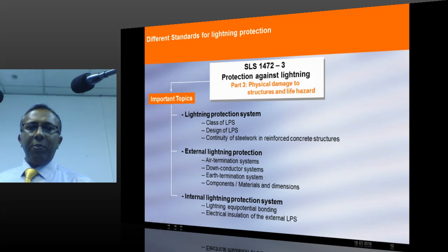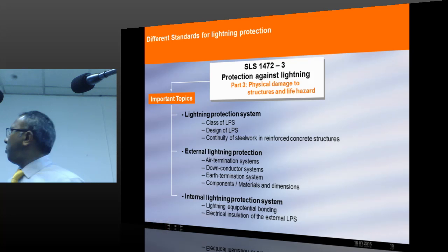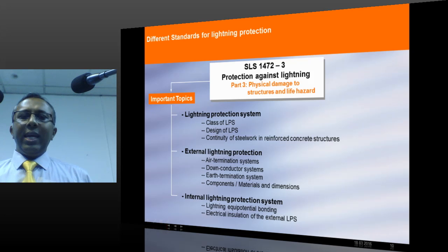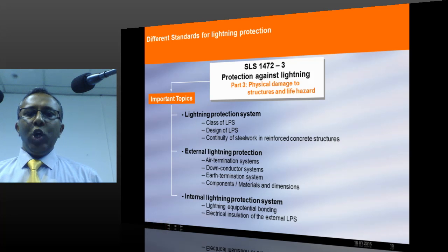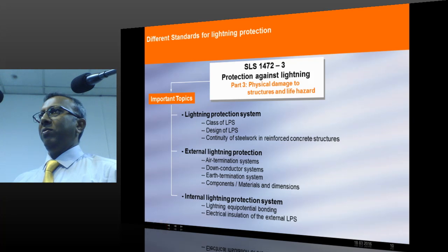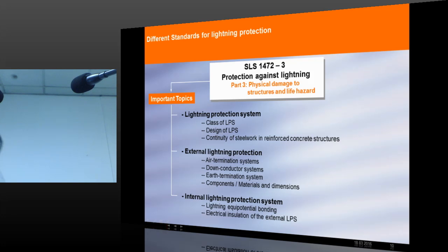Now we talk about part number 3. Part number 3 talks about external lightning protection, air termination system design, down conductors, earth termination, and components, materials, and dimension. Very important for you. This particular chapter, components, materials, and dimension, explains whether you need to use steel or copper or aluminium, under what condition, what dimensions you can choose, whether it's a flat conductor or a round conductor, and what kind of connections are required. These are explained very well in this particular section of the standard.